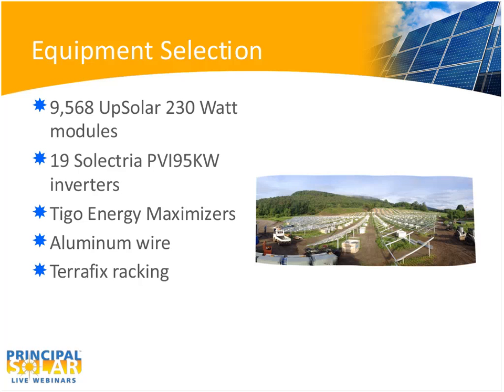We used aluminum wire, which is somewhat discouraged in a lot of circles, but because we increased the size of the wire, in some cases several times over what was needed, there was no safety issue. The racking was a Terrafix design, involving an earth screw and then three in portrait. The rack lengths actually vary quite a bit.